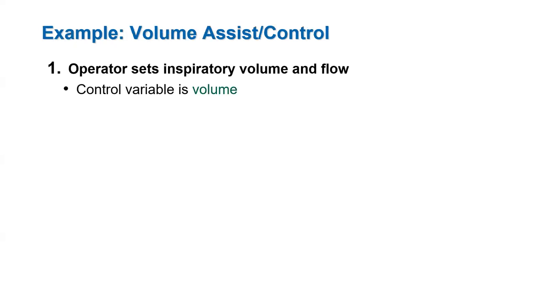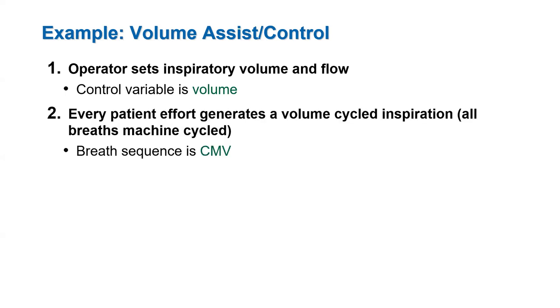Perhaps the most common mode used in the world is what is often called volume assist control. Just as an example, the first step in classifying this mode is to know that the operator sets both tidal volume and inspiratory flow. This is the definition of volume control. Next, we note that every patient trigger effort results in a volume cycled breath. Volume cycling is machine cycling. From maxim six, we know that a machine cycled inspiration is one criterion for a mandatory breath. Hence, we know the breath sequence is continuous mandatory ventilation, CMV.